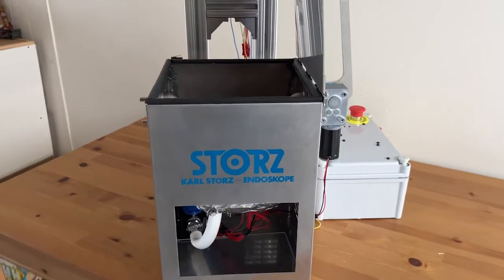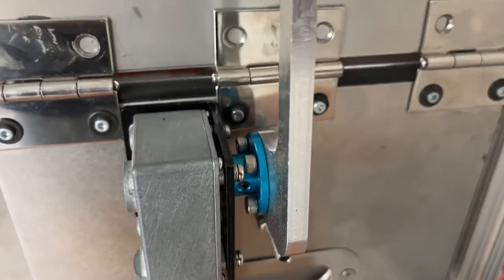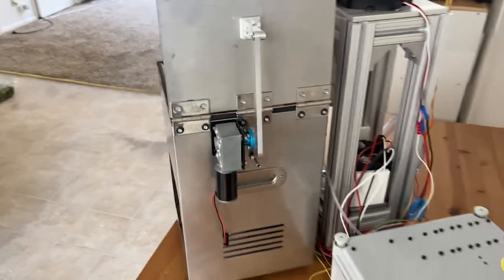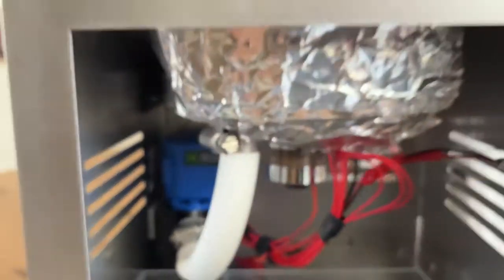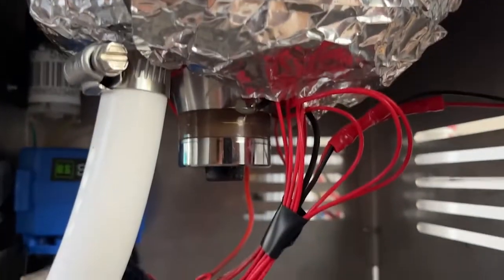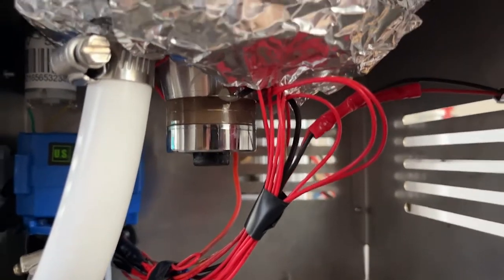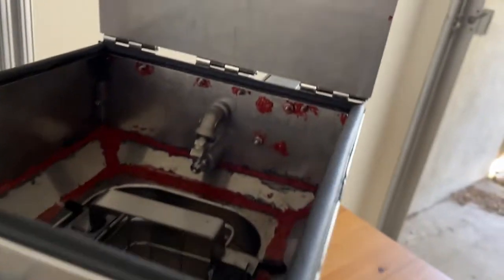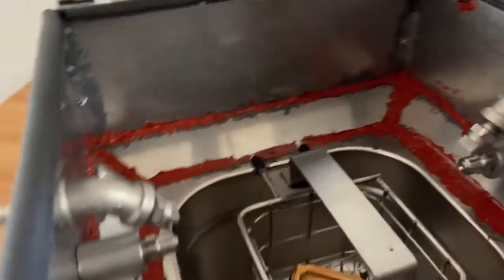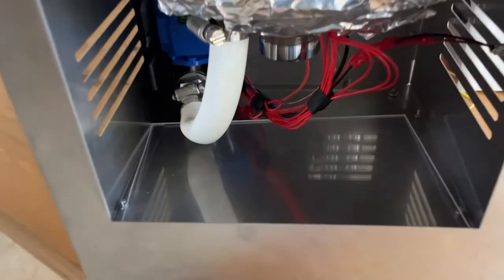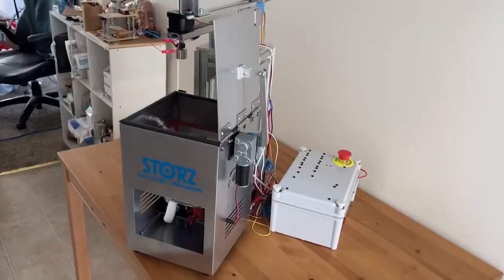Next, let's go to the custom chamber, which has a powerful non-back drivable worm gear motor to keep a watertight seal along the lid, 2 solenoid valves to control flow rate of the water, a peristaltic pump to bring in Neodisher for chemical degradation, heating pads and a thermocouple for thermal degradation, an ultrasonic transducer and pressurized jets for mechanical degradation, 360-degree valves for chamber rinsing, and of course a ball valve for the drain.